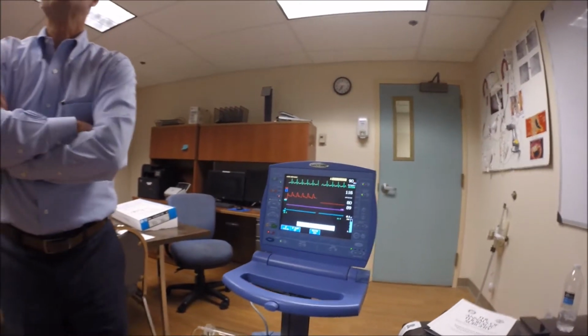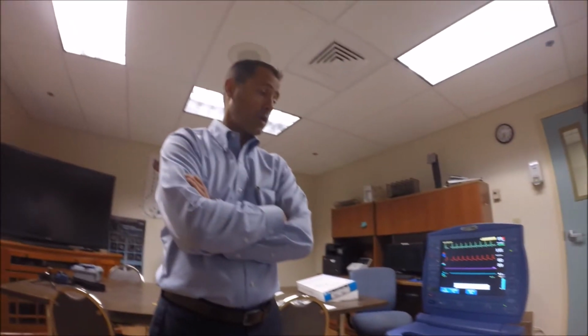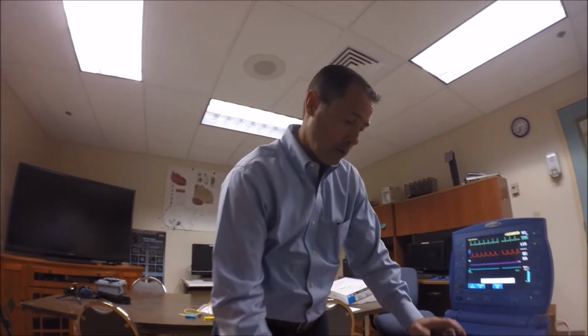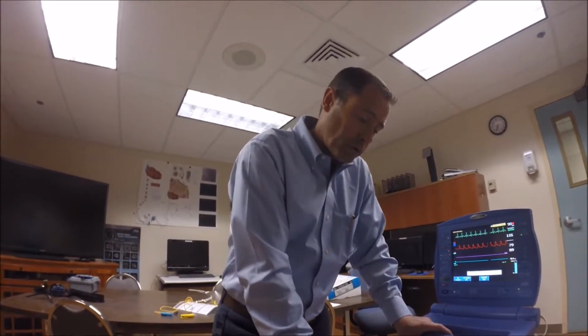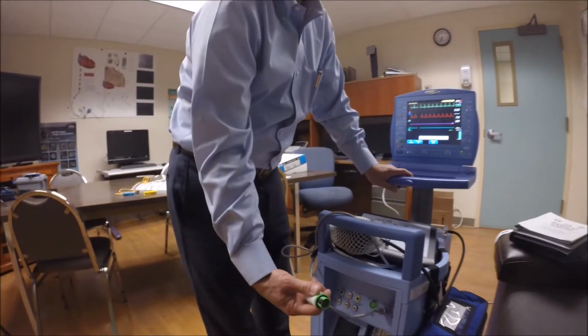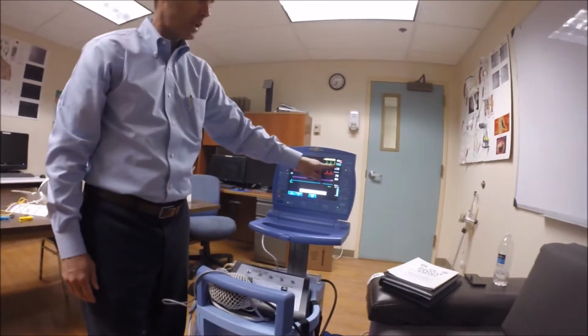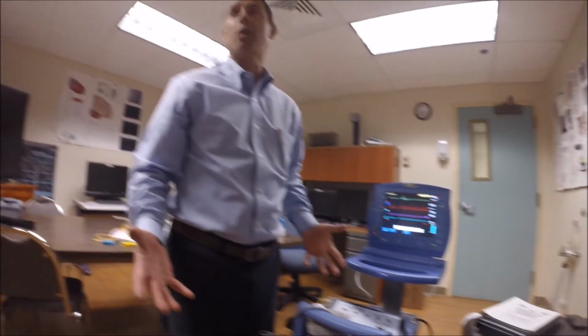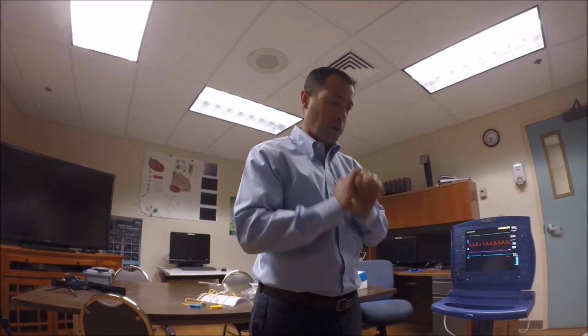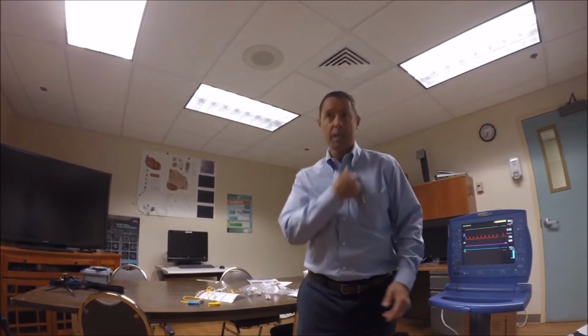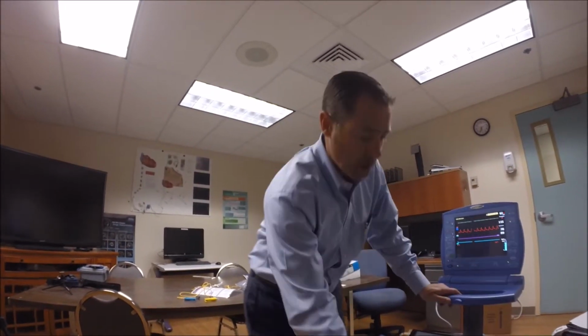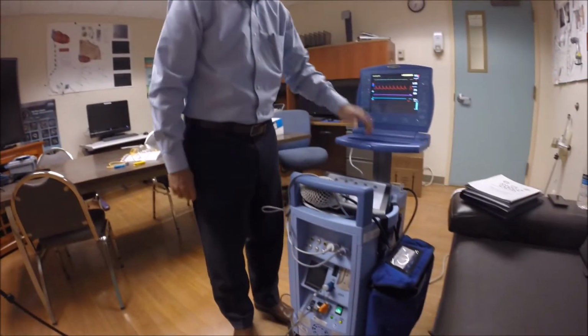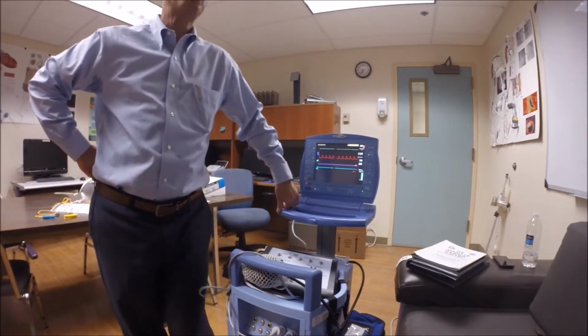So for transport, for CPR purposes, no need to manually mess with the trigger. That's right, because it'll select pressure automatically for CPR. And what if you get ROSC, and will it find its trigger back to where it belongs? So what I suggest then is to pull your ECG cable out, because when you pull your ECG cable out, it'll automatically switch to an AP trigger. Just leave it off, because you're okay signaling off of an arterial pressure waveform, certainly during compressions. And when your patient comes back, your fiber optic is a high fidelity AP. Now, if you feel like you're okay to reconnect, then you can certainly reconnect your ECG cable and get your waveform back. But yes, you can trigger just as effectively off of an AP signal.